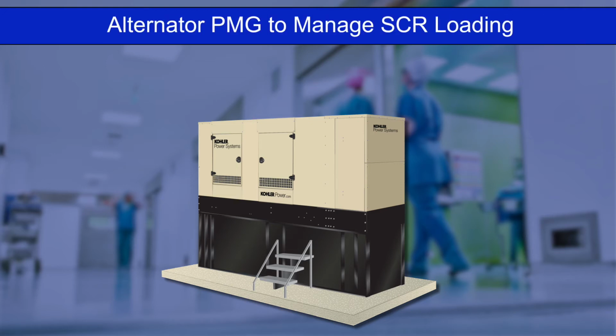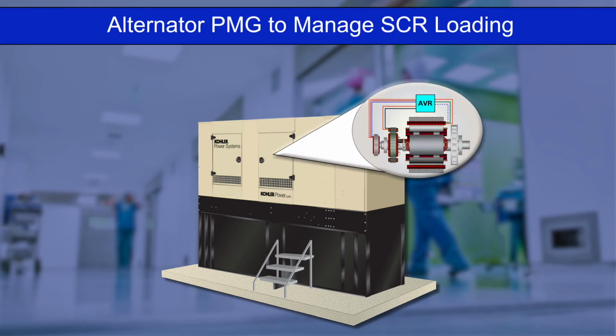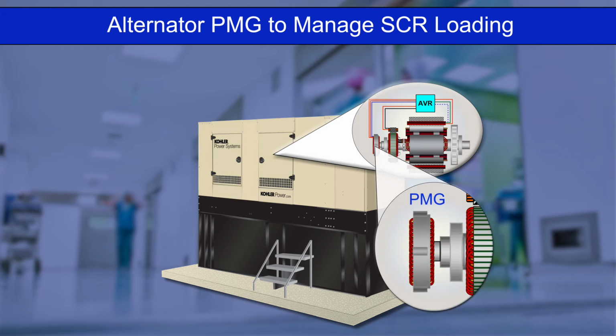Healthcare connected loads with a high percentage of SCR loads can produce voltage transients that can have an adverse effect on a generator's voltage regulation system. To manage these transients, the generator should be fitted with a permanent magnet generator (PMG) excitation system.